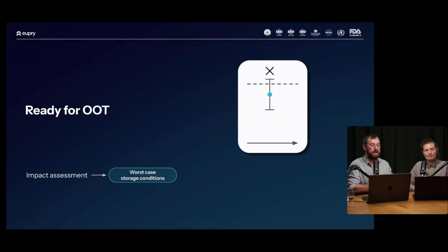The easiest way to do this is saying, okay, our sensor has drifted 0.1 degrees outside of our tolerance. What would that mean? Let's say the initial calibration was fine, and then after a year it is 0.1 degrees out of tolerance. The most basic and easiest thing to do is basically saying, let's assume that it was constantly 0.1 degree outside. That's our worst case storage conditions. So what does that mean? Let's look at our temperature data and say all of the temperatures were 0.1 degree higher than what we thought. What is the impact on the product? In most cases, you're never going to be that close to the alarm limit or your tolerance limit. But let's just say it is. So you can very simply export your data and just add 0.1 degrees if that's your evaluation.